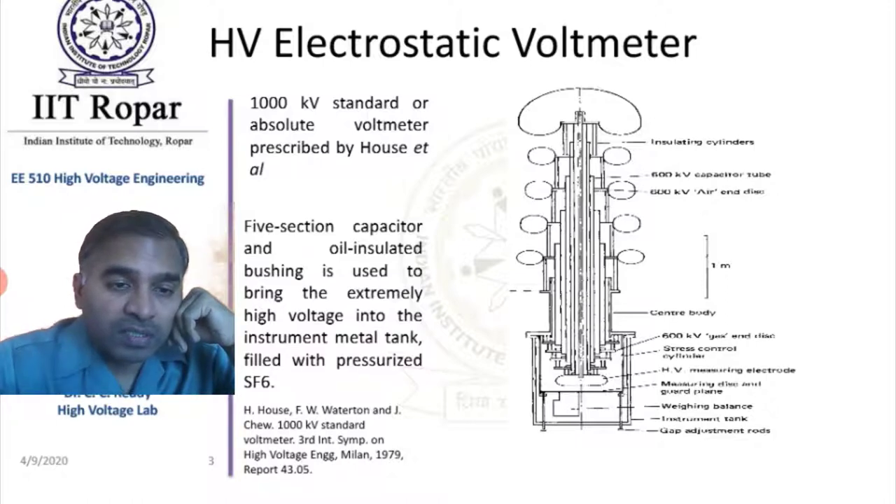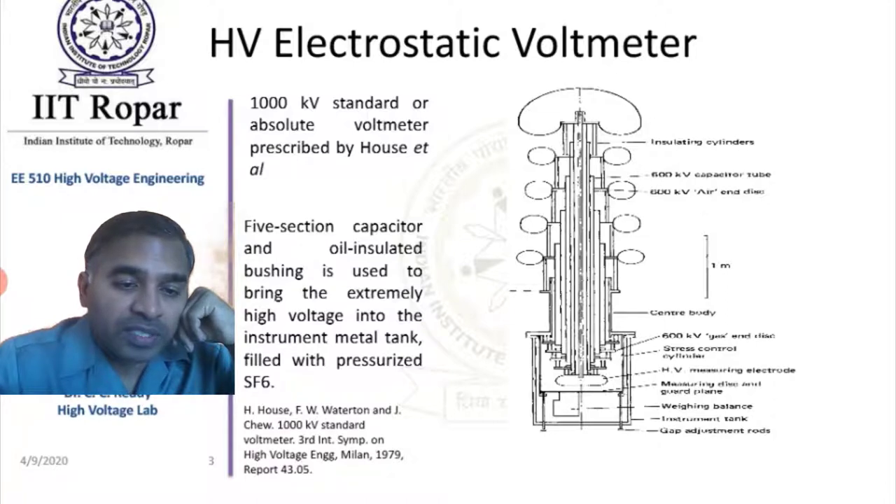This is a 1000 kV standard absolute voltmeter prescribed by House et al. It is mentioned that a 5-section capacitor and oil-insulated bushing is used to bring the extremely high voltage into the instrument tank — a metal tank filled with pressurized SF6 gas.